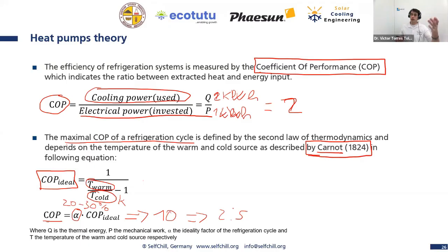We will invest 1 kilowatt hour of electricity and get 2.5 kilowatt hours. But this depends a lot on the temperatures. If the delta temperature is low, the COP will be high. If the delta temperature is high, then the COP will be low. We need to understand this, and this is done by the COP ideal. So here you have an equation to calculate your COP based on the warm temperature and on the cold temperature.